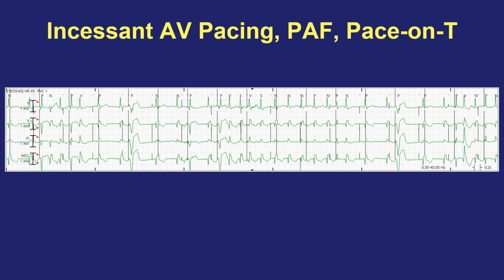Here is another problem to troubleshoot, and it looks a little bit confusing because this is a very busy telemetry strip, but let's see what's happening. And the first thing I want to call your attention to is what's happening with pacing here. If you look carefully, you're going to see that there's two pacer spikes, atrial pacing and ventricular pacing, and it's occurring all the way through this strip at an absolutely regular interval, and it's completely oblivious to native heartbeats that are occurring in the atrium or the ventricle. This is dual chamber pacing that's occurring with no sensing happening.